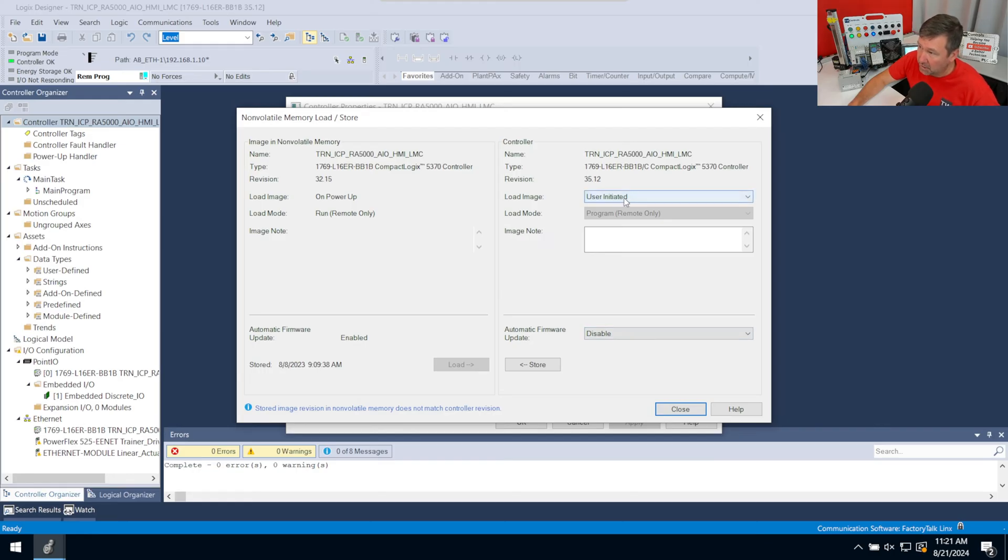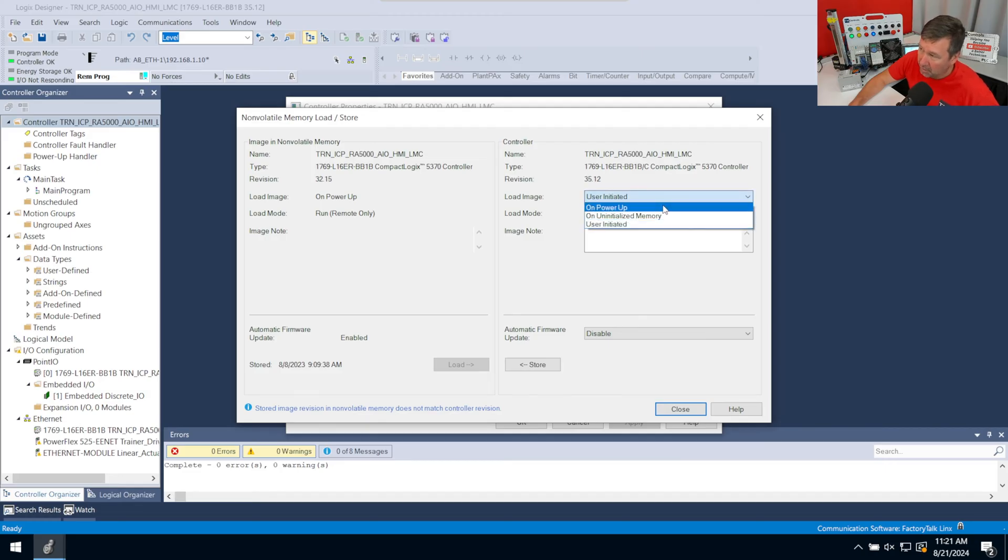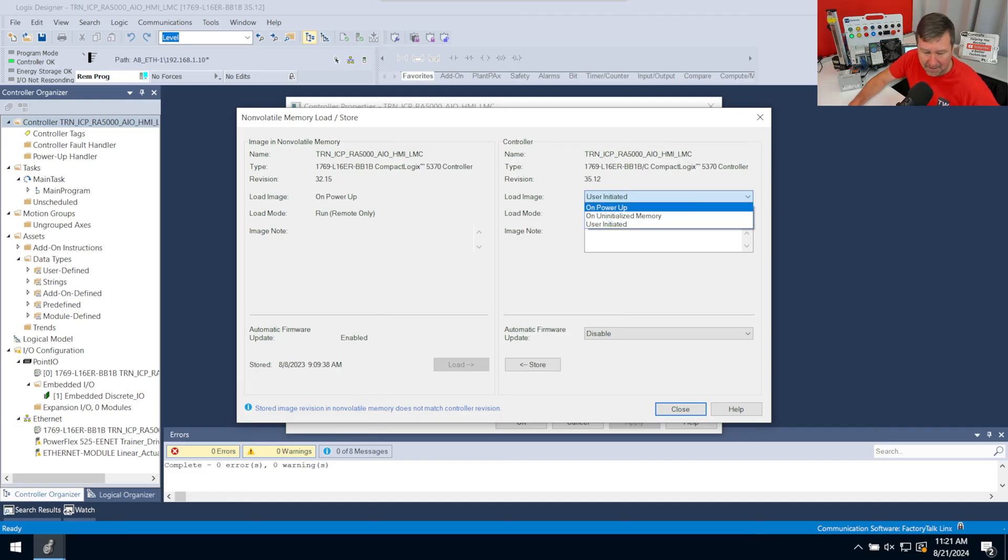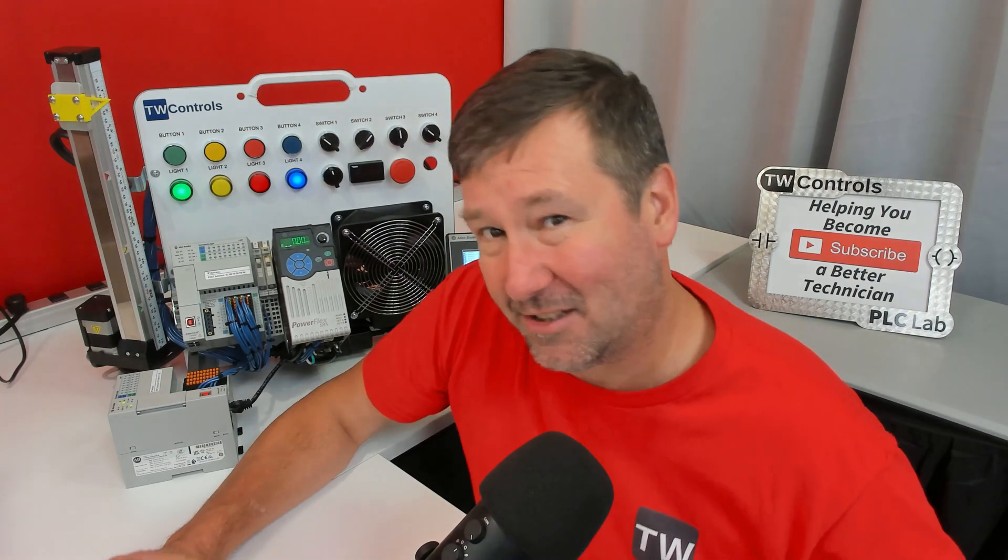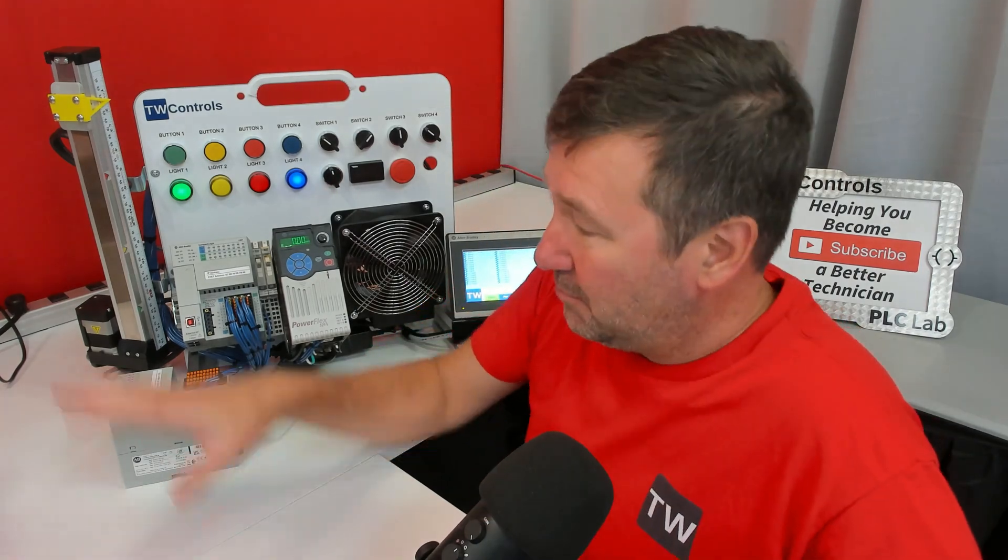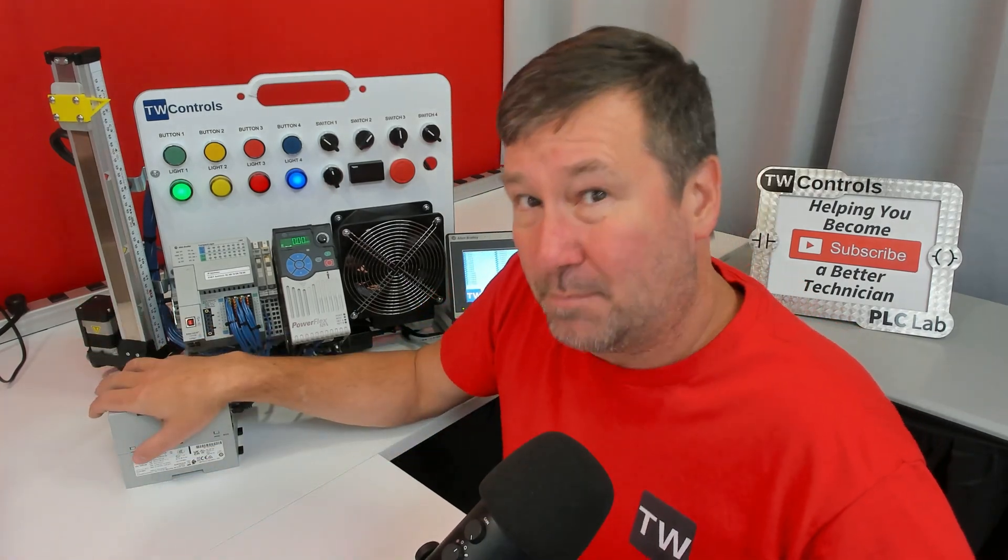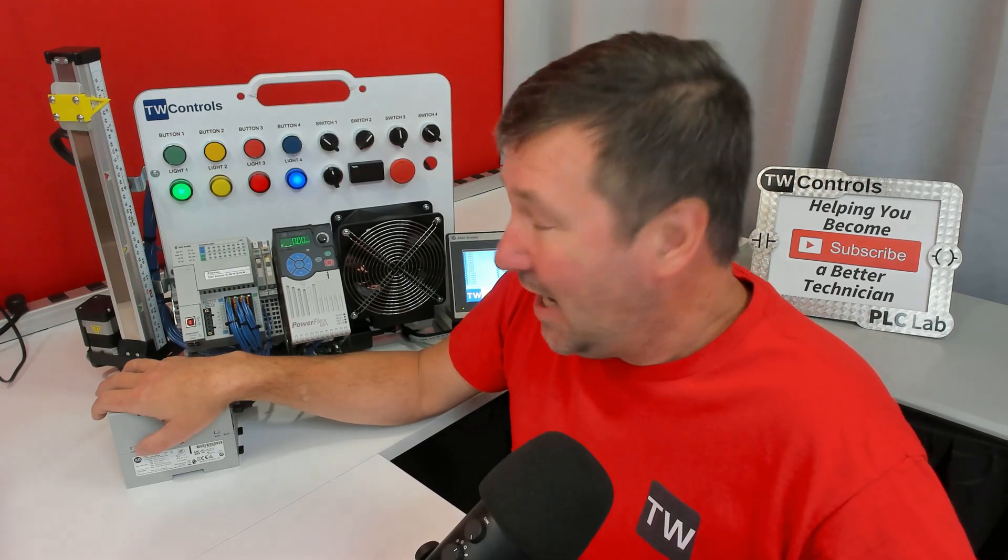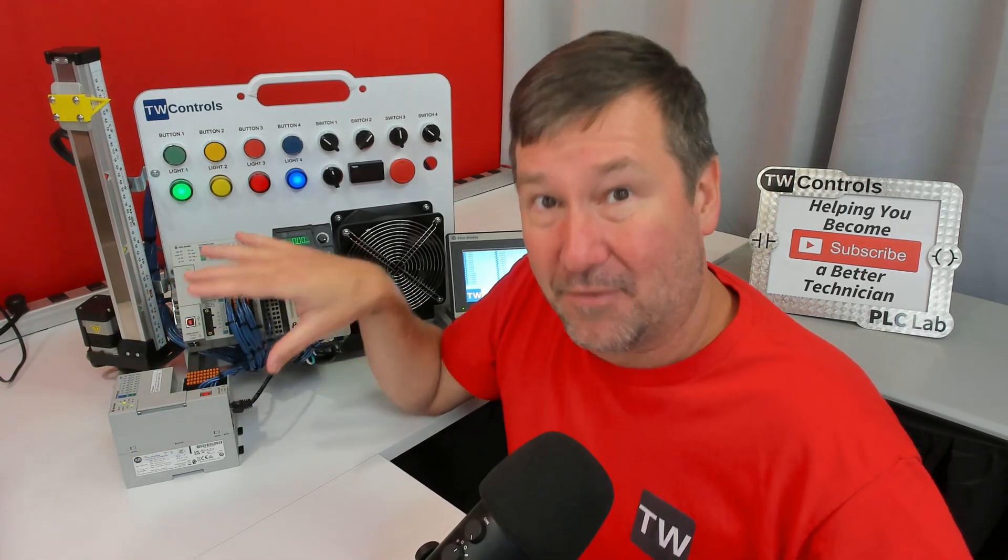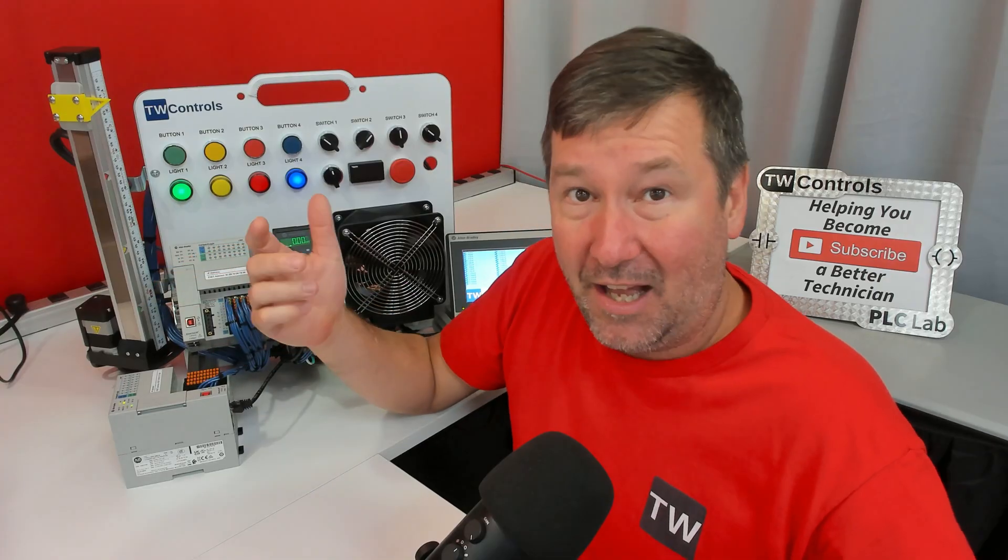First of all, we could set this on here just as user initiated. And what that means is you're going to be right here and you're going to load from here. Or we can do it on Power Up, which is actually what we do on our trainers. Or we could do it on uninitialized memory. Now, let's talk for a second about the difference between Power Up and uninitialized memory. Uninitialized memory would be like I just pulled this out and did it. And arguably, that is perfectly fine for even us setting them up. But a lot of times when I'm doing videos for you, I'll go grab a PLC, just like I went and grabbed this one.